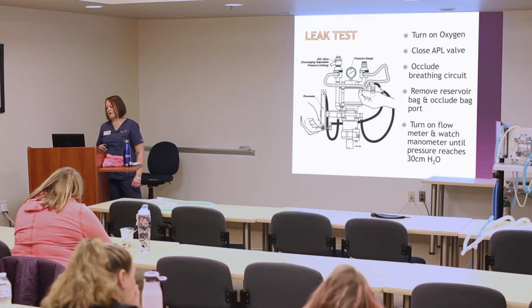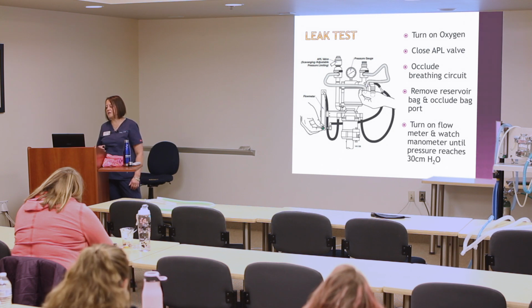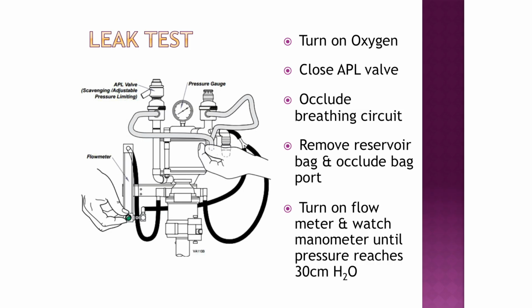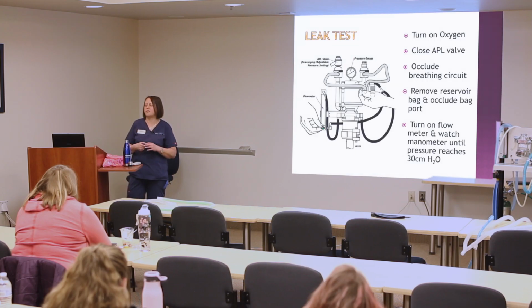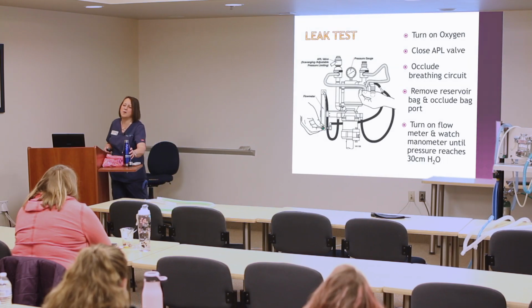But yeah, I will show you guys how to do that at the end here. And this says to pressurize it to 30. I mean, I will never in my right mind give a breath to 60, so I don't really care if the machine leaks at 60. I don't want it to leak at the most commonly utilized pressures, which is going to be under 30.